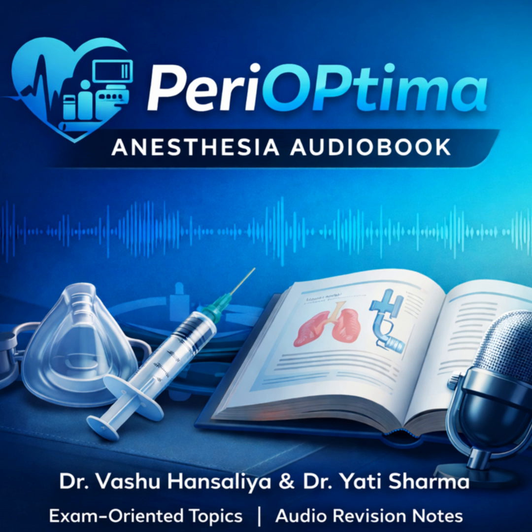Let's move to Part B, Basic Principles. This seems to be the mental framework we need before we even touch a knob or a dial. This is a very high-yield concept. I can't stress this enough. If you are asked to draw the machine, and you will be, you don't draw a picture of a cart with wheels and drawers. You draw a schematic. You draw a schematic based on pressure.